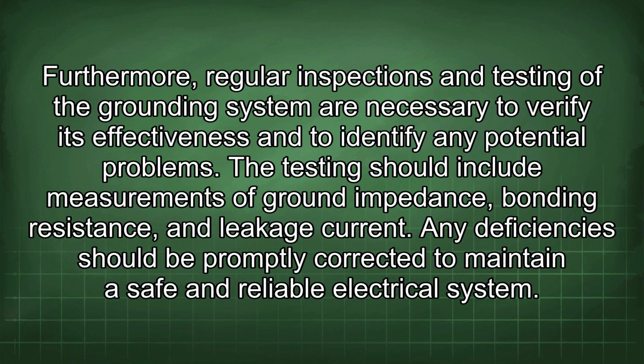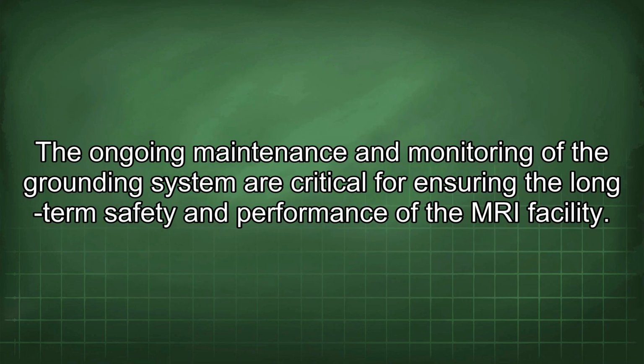Furthermore, regular inspections and testing of the grounding system are necessary to verify its effectiveness and to identify any potential problems. The testing should include measurements of ground impedance, bonding resistance, and leakage current. Any deficiencies should be promptly corrected to maintain a safe and reliable electrical system. The ongoing maintenance and monitoring of the grounding system are critical for ensuring the long-term safety and performance of the MRI facility.